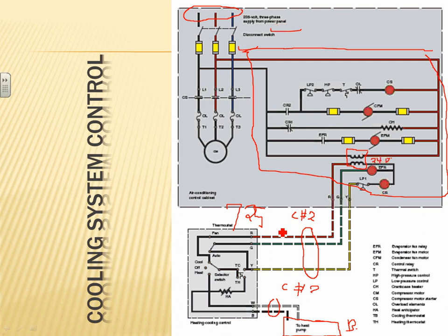With some exceptions, you can't put them with the power circuit inside the pipe. You can attach the wire to the pipe if it's functionally associated, if it's going to the same machine like this, attach it to the outside of the pipe, but you cannot put it inside the pipe. Typically, we pipe them separately, the control and the power. Any comments, guys? Any questions about that?